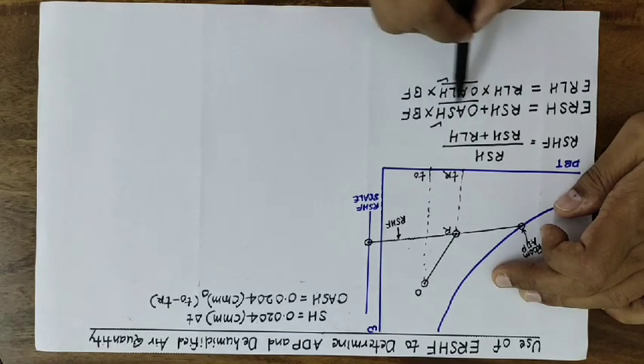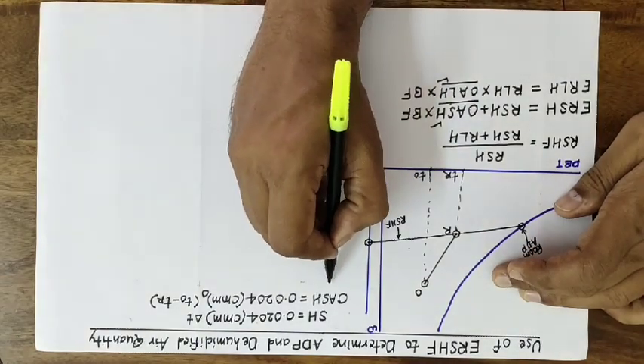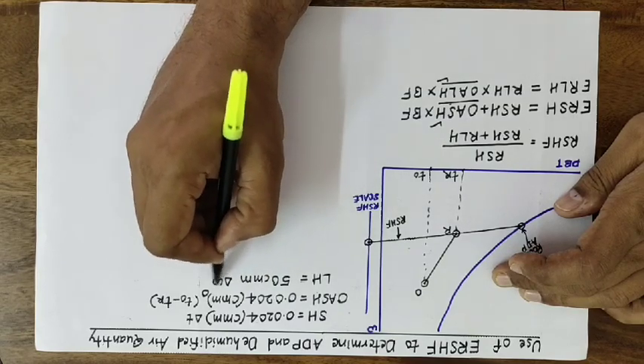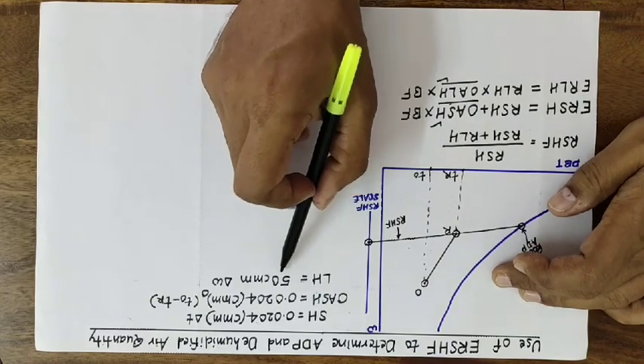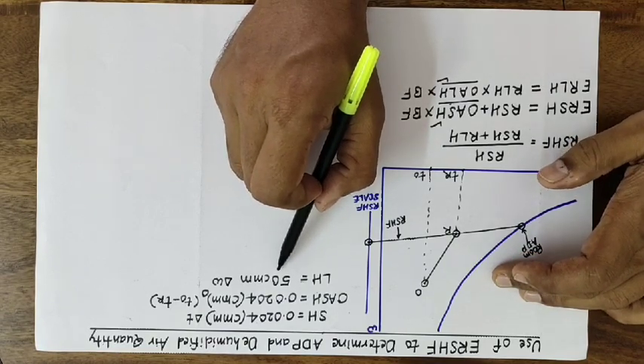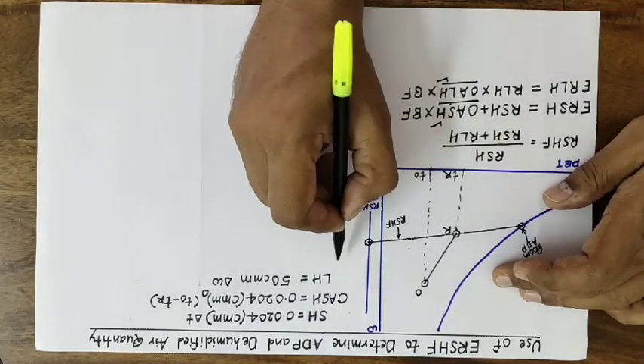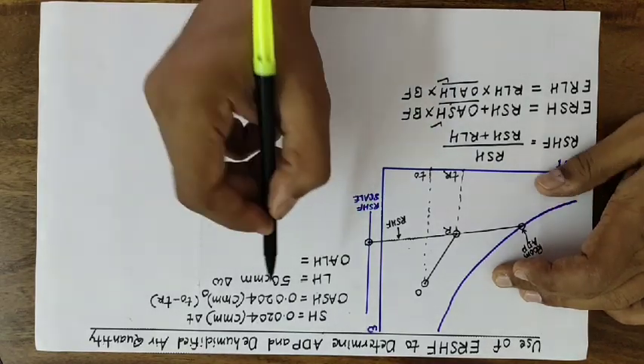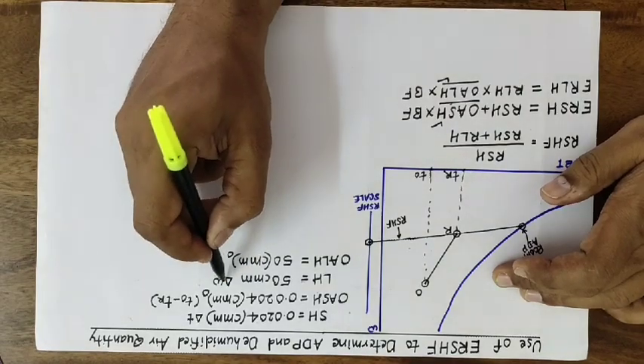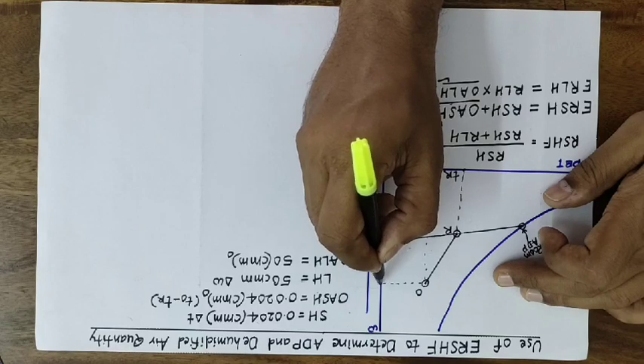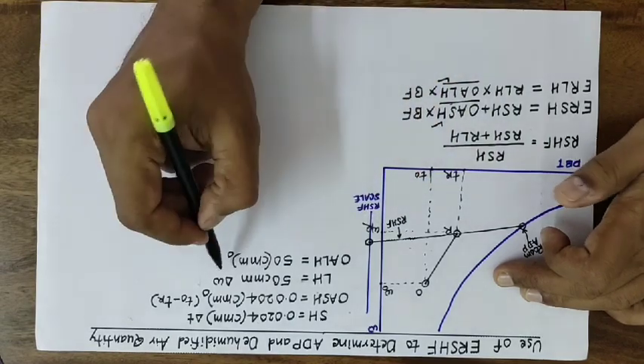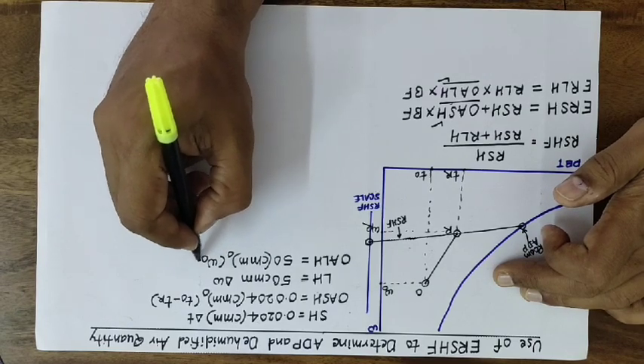Similarly, we have the latent heat formula: latent heat = 50 × CMM × Δω. The factor 50 comes from using average air density of 1.2 and the enthalpy of vaporization at the reference state of 0°C (approximately 2500 kJ/kg). The same formula is used for outside air latent heat: OALH = 50 × CMM_O × (ω_O − ω_R), where ω_O is the specific humidity of outside air and ω_R is that of room air.